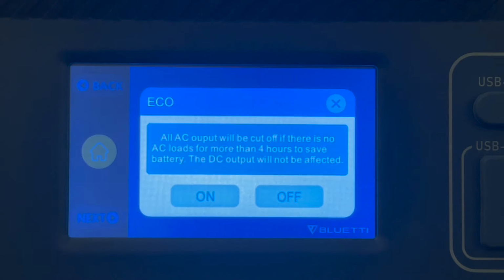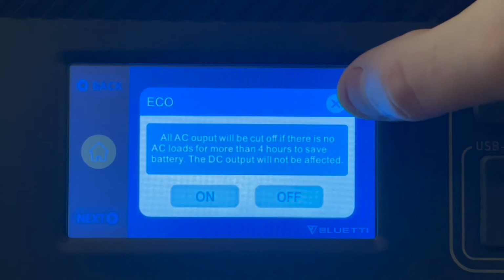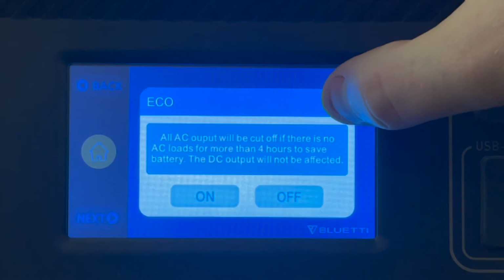One nice thing about the AC500 is it will power back on automatically when the solar comes up the next day. So if you've got a large solar array and you don't need the thing running overnight, you can turn on eco mode. It will automatically turn off at night, and then it will automatically turn back on in the morning. The only thing it does not do is automatically turn the AC output back on when it turns on in the morning. So if you want it to automatically have your AC output back on, you're going to have to do some additional work. But the eco mode does not do that.